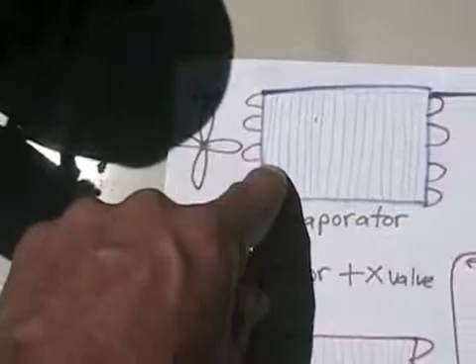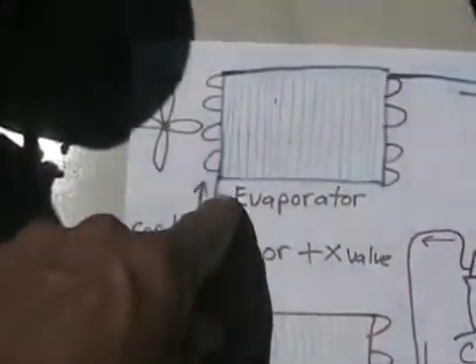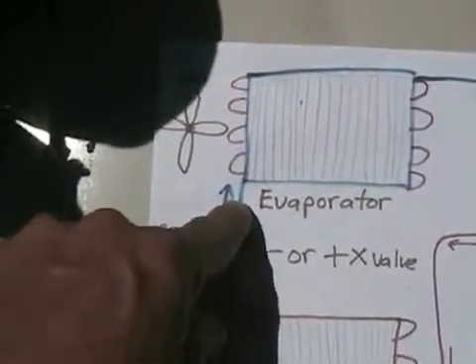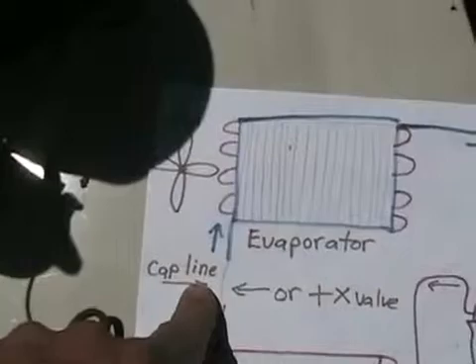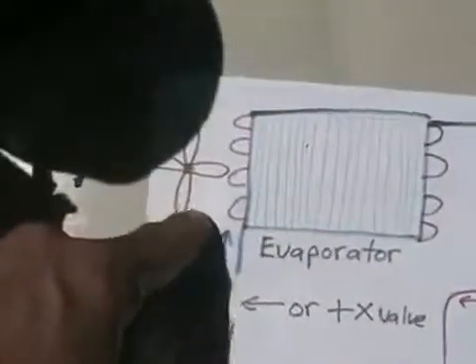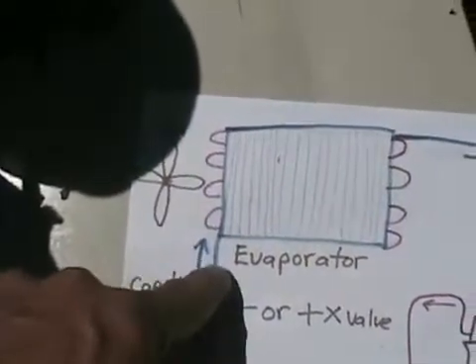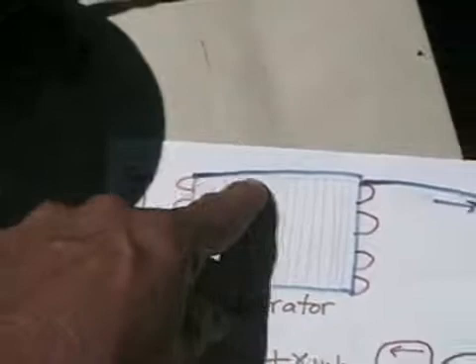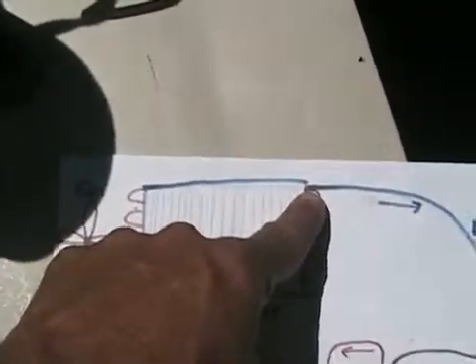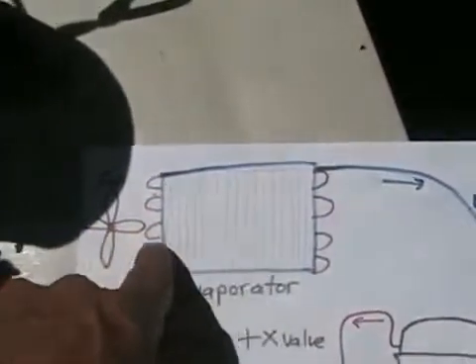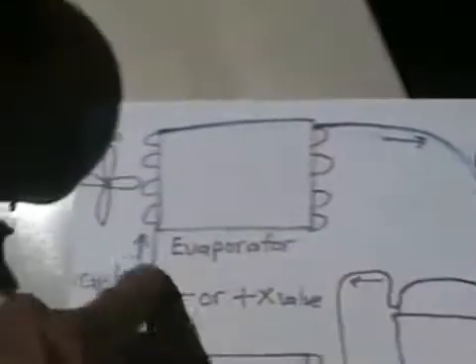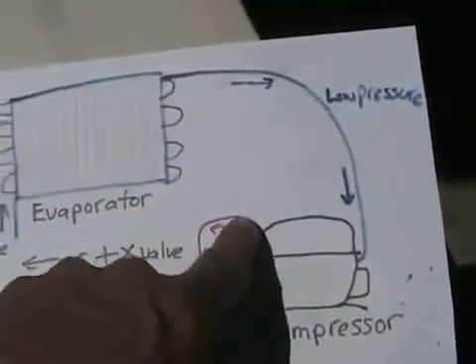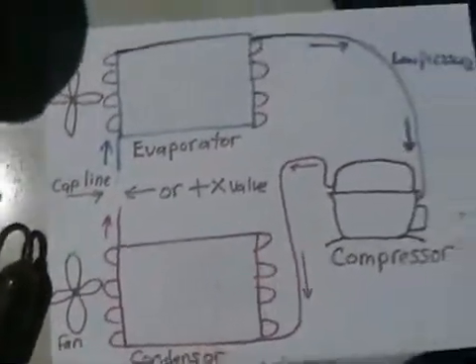By the time the freon travels through that tube and reaches the evaporator, it enters much larger diameter tubes — the largest in the air conditioner — giving the liquid freon room to expand. When a liquid turns to gas, that's called evaporating, and it makes itself colder. The liquid freon bubbles and evaporates as it travels through all the little tubes, and by the end of the radiator it's pure gas, warmed to room temperature. That gas, now containing more heat than before, returns to the compressor to be recompressed, and the heat is exhausted by the condenser. That's how all systems work.